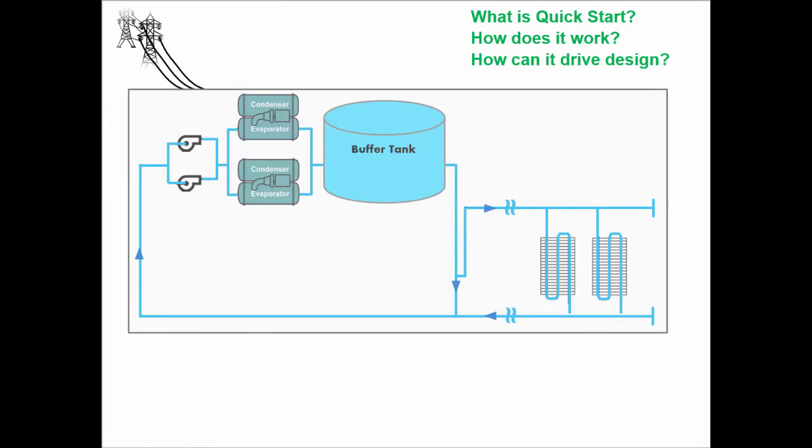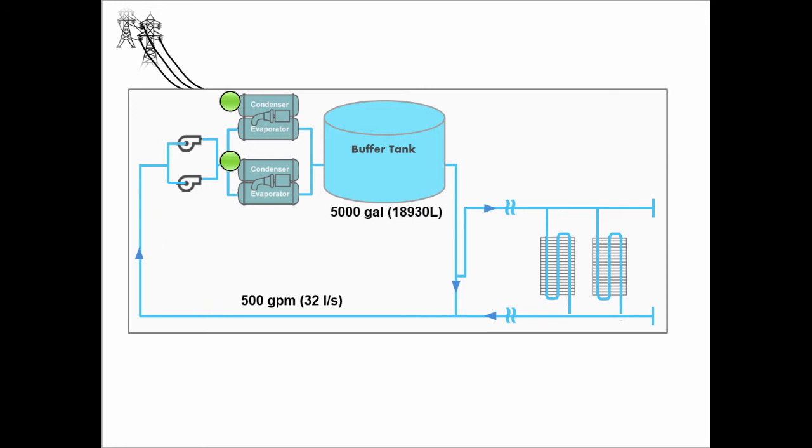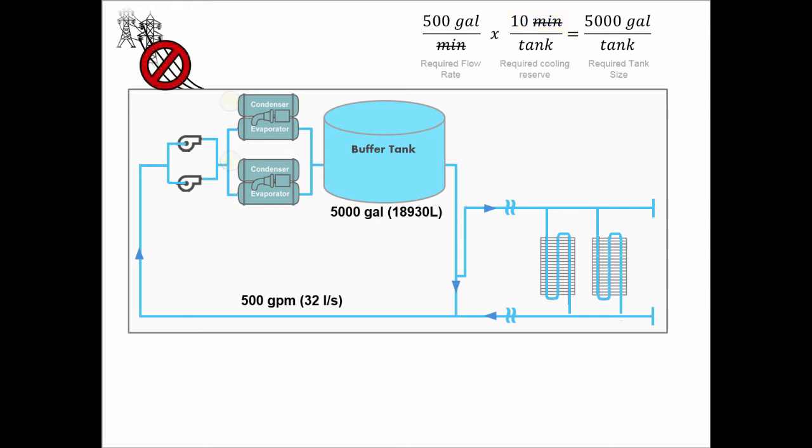Now getting back to one of the original questions, how do chillers start and load times relate to buffer tank sizing? Well, consider the example of a data center with a 500-gallon-per-minute chilled water requirement. After the chilled water leaves the chiller, it flows into a 5,000-gallon tank, which based on the flow rate need, should be able to provide approximately 10 minutes of chilled water, meaning if there was a power loss, this reserve could fill the required cooling gap until the chillers were back online and meeting the required load.